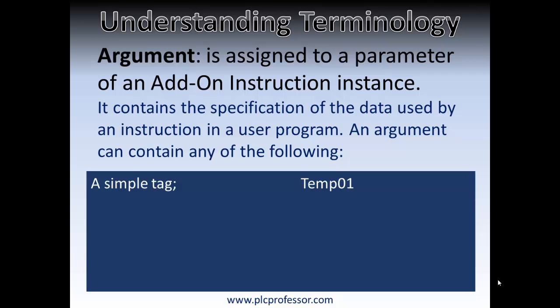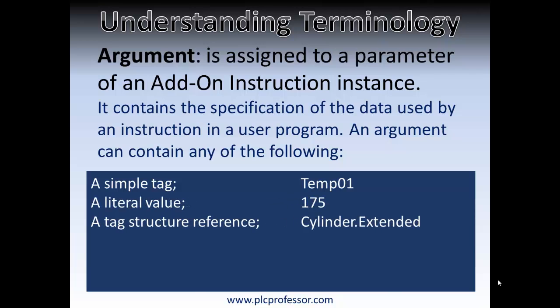An argument could be a simple tag, or it could be a literal value like a constant. It could also be a tag structure reference. For example, the argument cylinder.extended — where extended is an element in the data structure cylinder. If you think of a cylinder in terms of different pieces of data, you've got extended and retract: you told it to extend, you told it to retract, it's extended or retracted, or neither, or both.